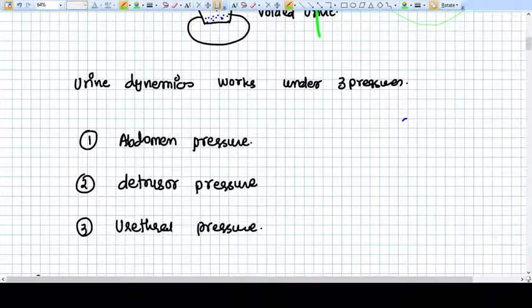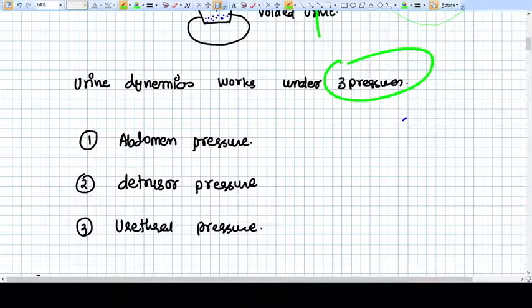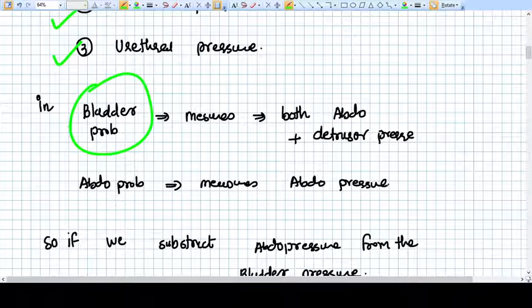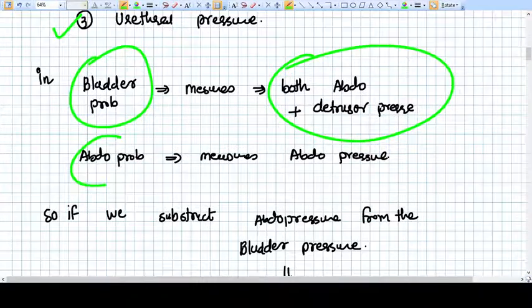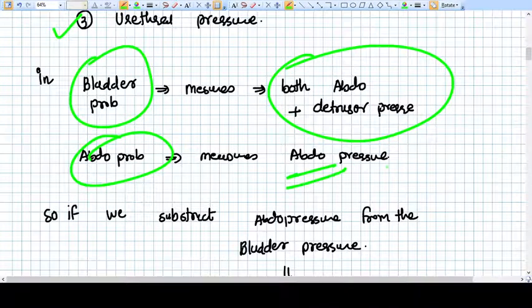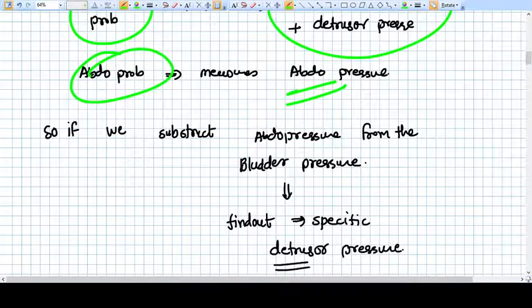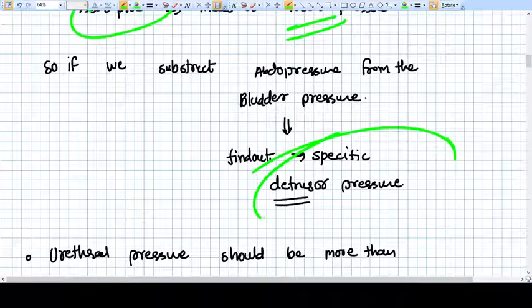Now, as we have described, urine dynamics work under three pressures: abdomen pressure, detrusor pressure, and urethral pressure. The bladder probe measures both abdomen and detrusor pressure. The abdominal probe measures only abdominal pressure. So if we subtract abdominal pressure from the bladder pressure, we will get specific detrusor pressure.